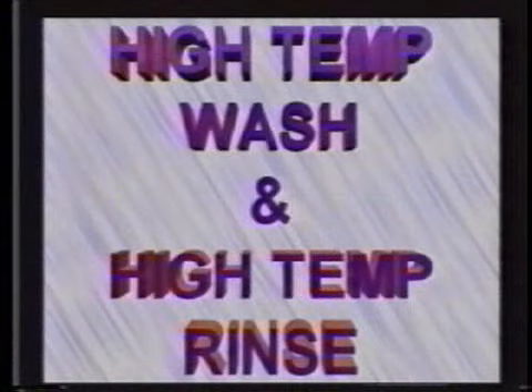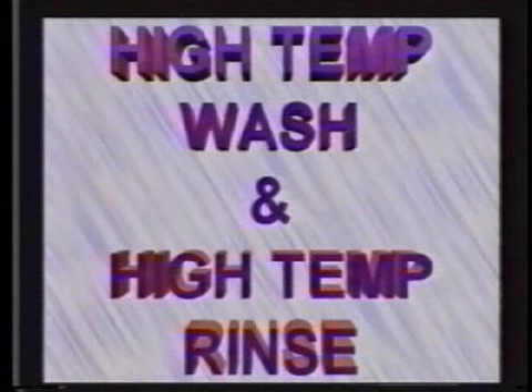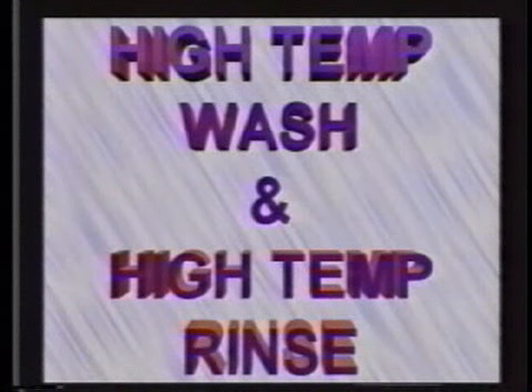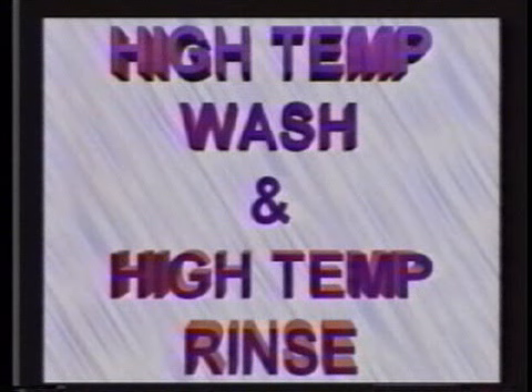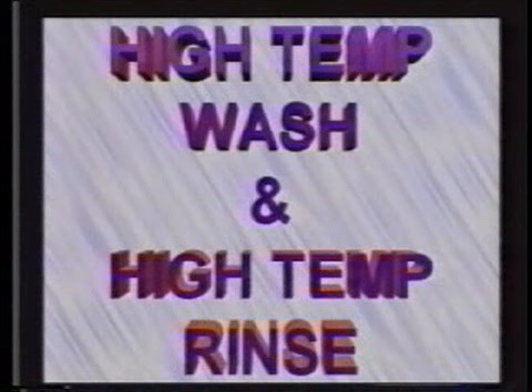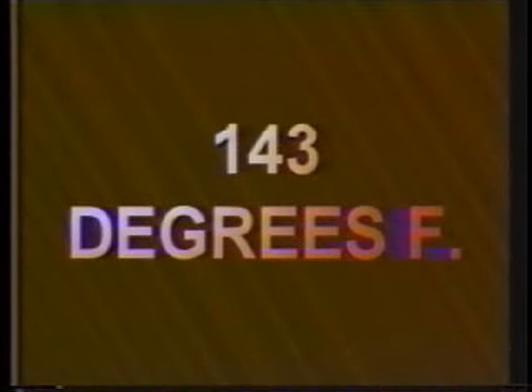If we look at the cycle chart again, you will find that the increment next to temp assure in the wash cycle is high temperatured wash, and in the rinse cycle is high temperatured rinse. These two functions must be selected by the user, as they do not occur automatically, but operate similar to the temp assure. Basically, they pause for up to 10 minutes, but instead of trying to heat the water to 136 degrees as in the temp assure cycle, the high temperatured wash attempts to heat the water to 143 degrees, and the high temperatured rinse attempts to heat the water to 145 degrees Fahrenheit.